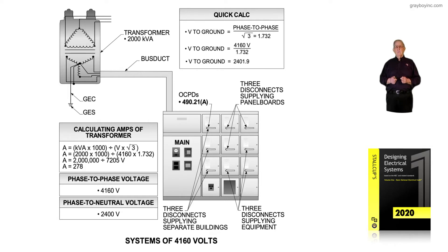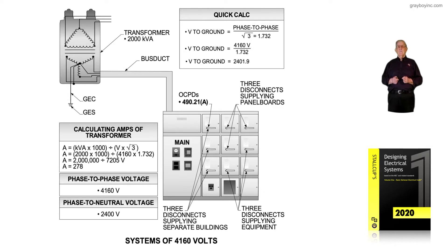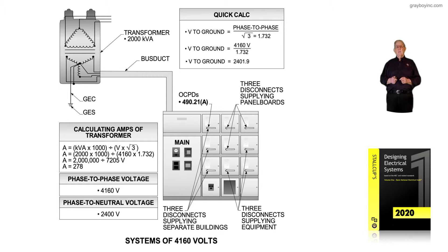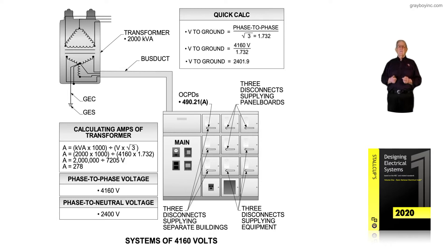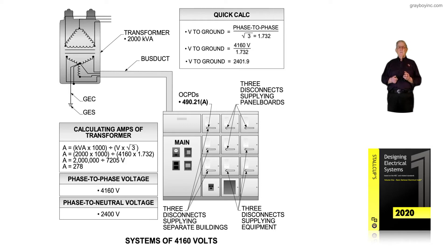The voltage to ground is obtained by taking the phase-to-phase voltage of 4160, divided by the square root of 3, because it's a three-phase system. That gives us 2401.9 volts, but the industry rounds that down to 2400 volts. So they call it a 4160/2400, three-phase, four-wire system, and the voltage to ground is 2400 volts.